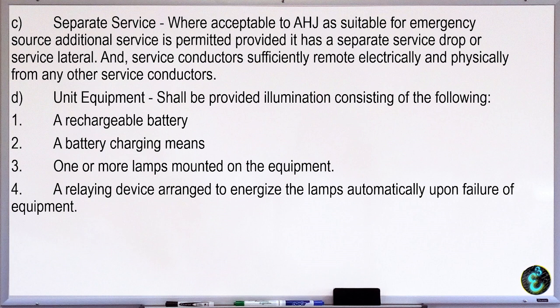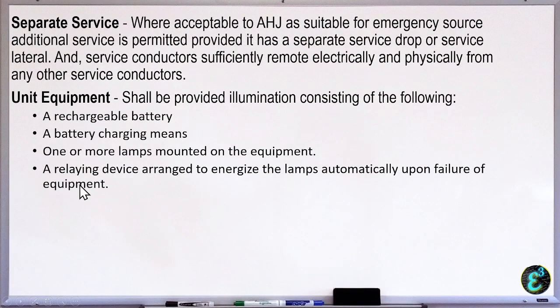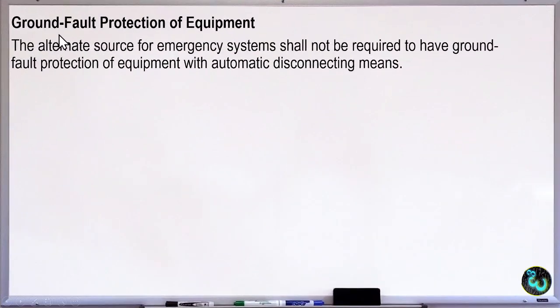Then the unit equipment shall be provided with illumination consisting of the following: a rechargeable battery, a battery charging means, one or more lamps mounted on the equipment, then a relaying device arranged to energize the lamp automatically upon failure of the equipment. Then, GFCI or ground fault protection of equipment. The alternate source for emergency system shall not be required to have ground fault protection of the equipment with automatic disconnect means. So the emergency system is allowed even without GFCI. That is for the emergency system only, as long as the normal system has GFCI protection.